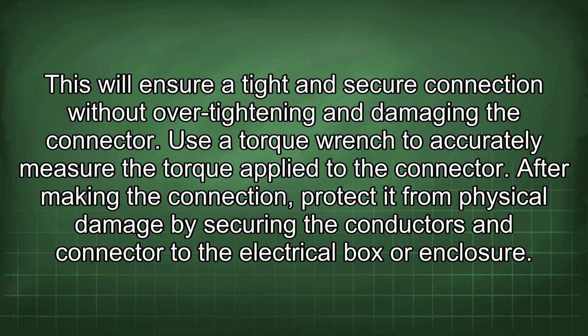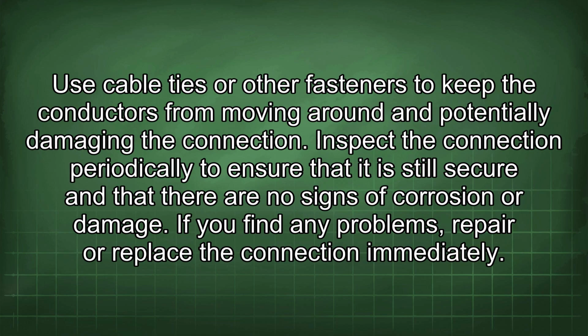After making the connection, protect it from physical damage by securing the conductors and connector to the electrical box or enclosure. Use cable ties or other fasteners to keep the conductors from moving around and potentially damaging the connection. Inspect the connection periodically to ensure that it is still secure and that there are no signs of corrosion or damage. If you find any problems, repair or replace the connection immediately.